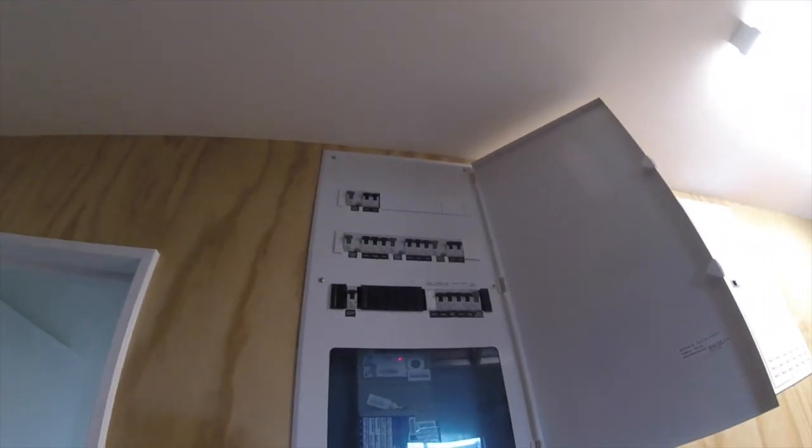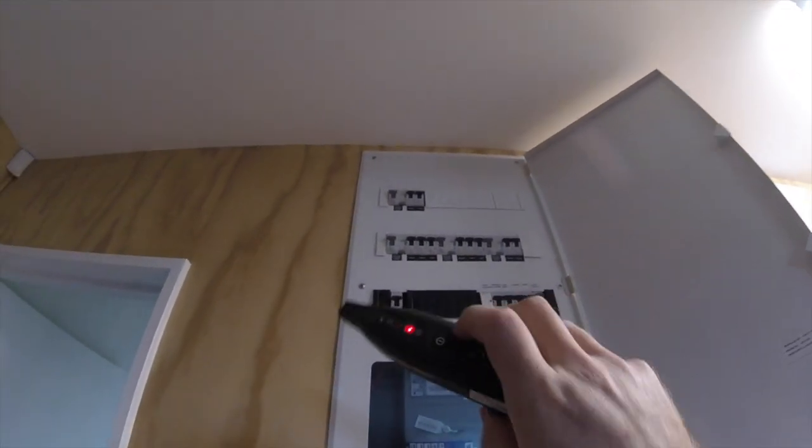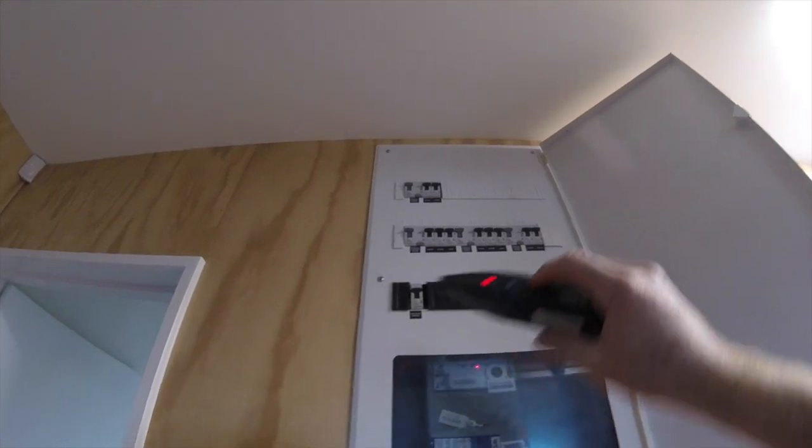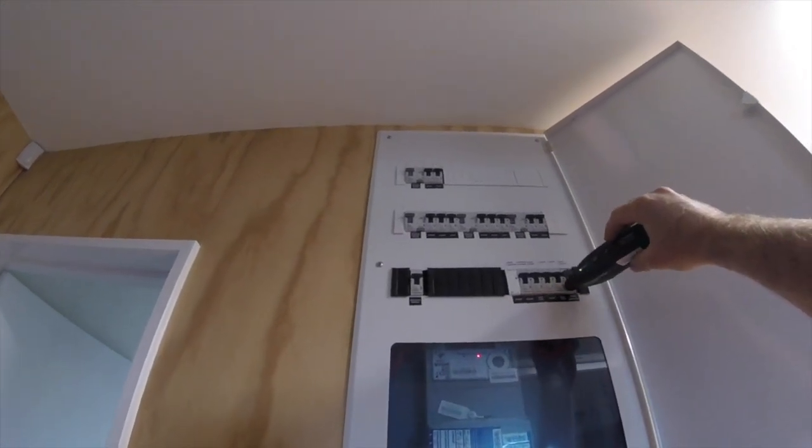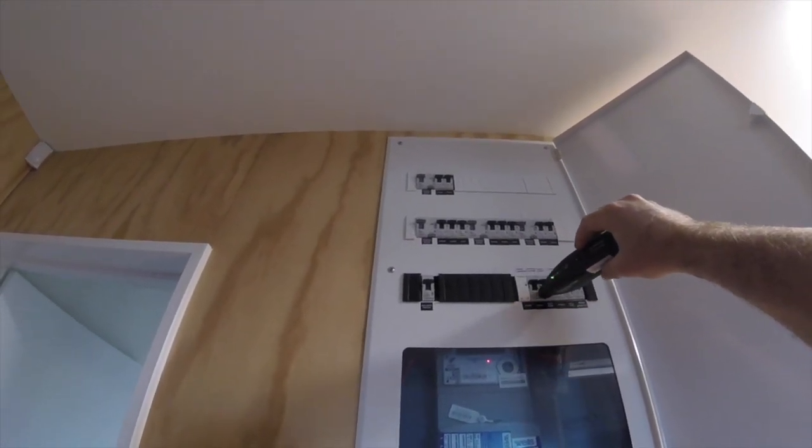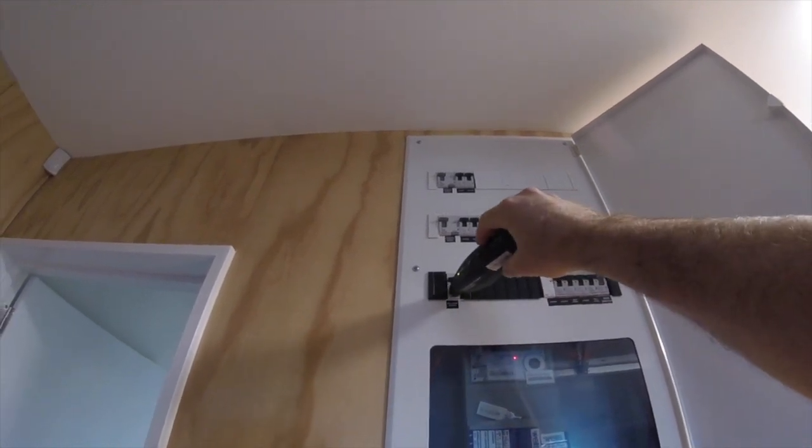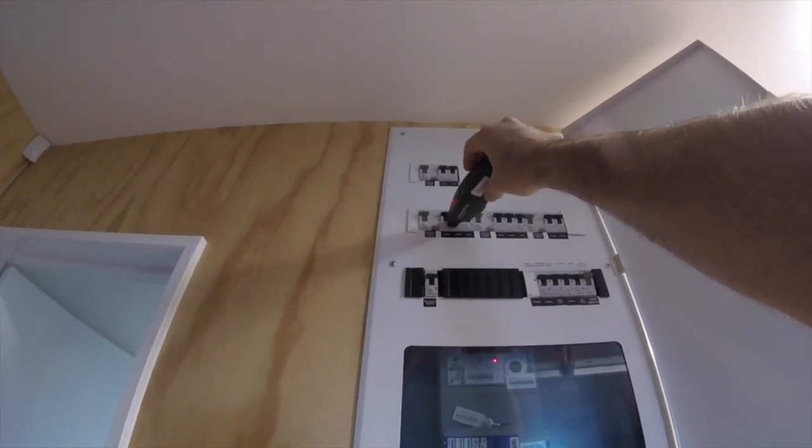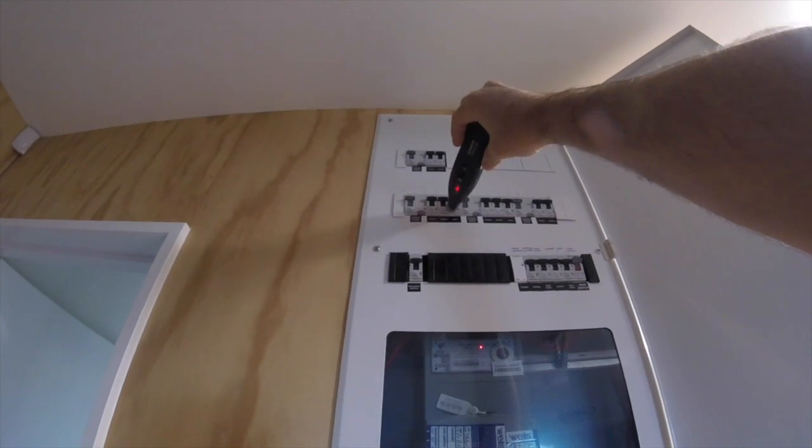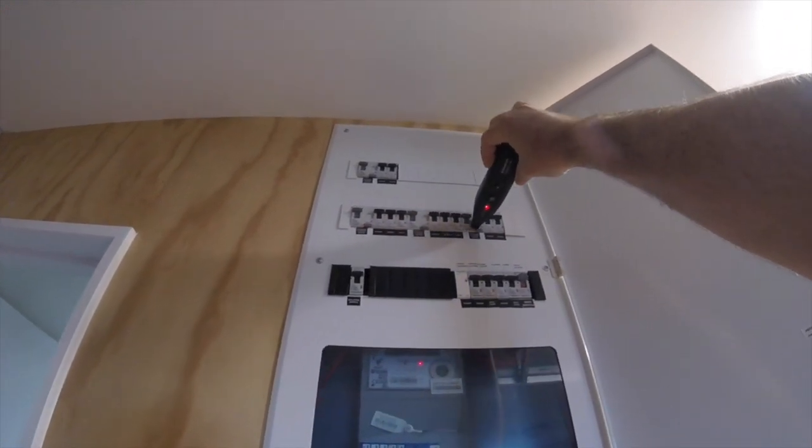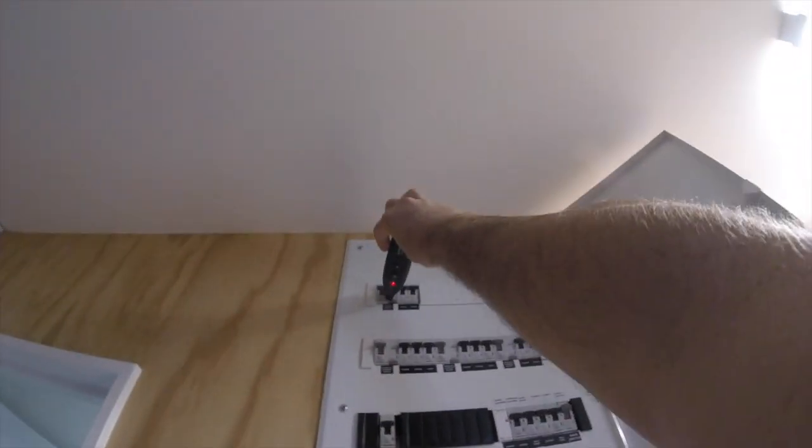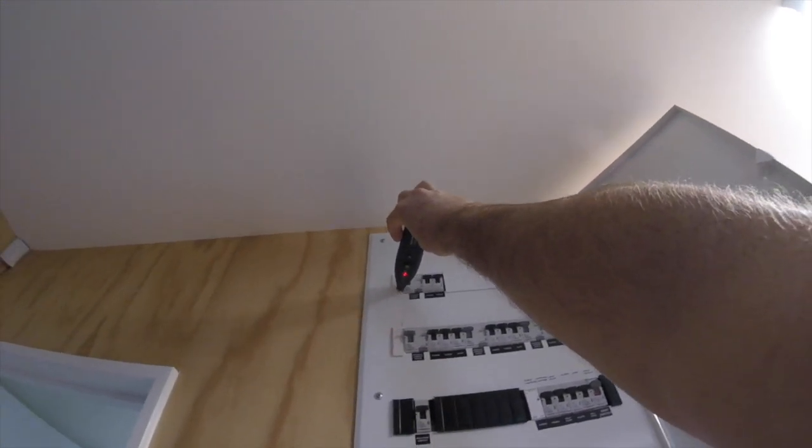And we'll see how accurate the KBEC tester is. The red light is on, the sad face is lit up, and then it's picking up the main switch, which a lot of circuit breaker finders quite often do. So sometimes, like I said before, it takes a while for them to pick up the right thing. So it's not picking up, we know that that breaker is the one, but it's not actually.